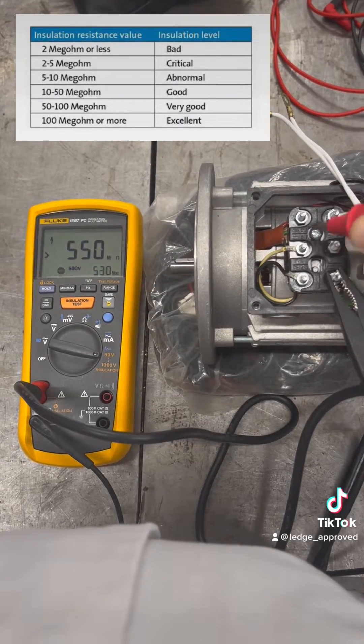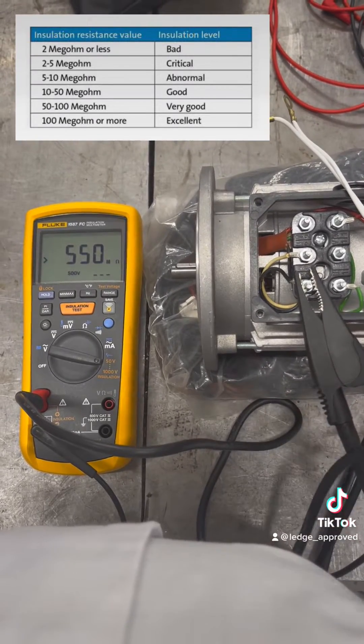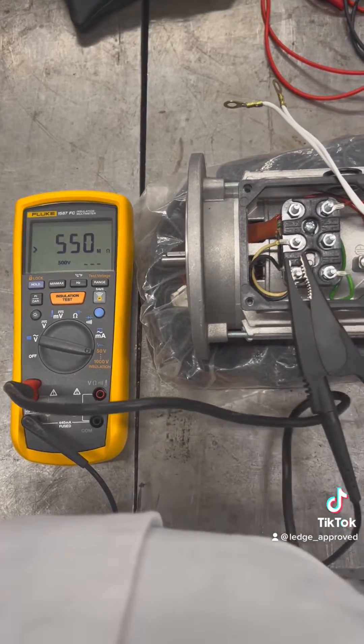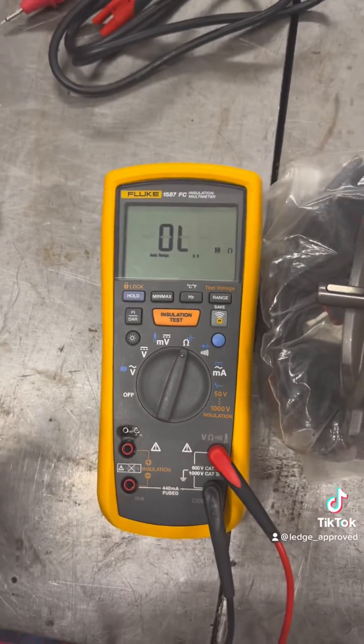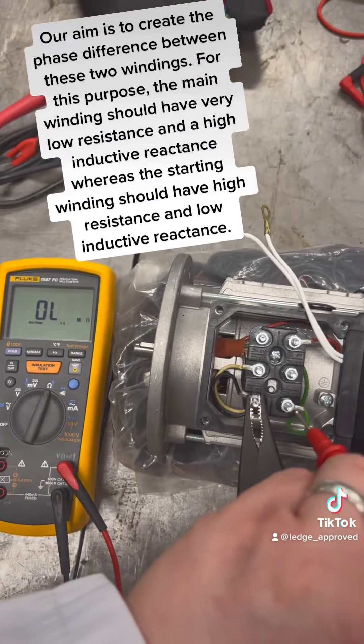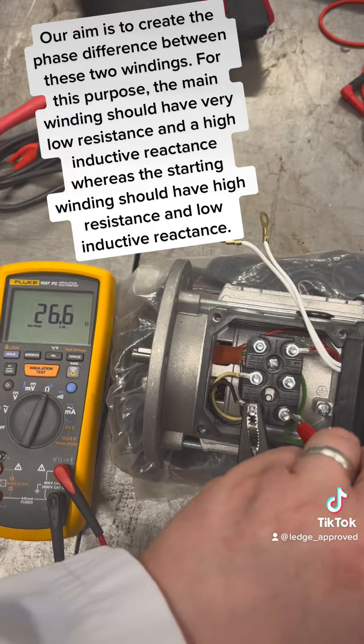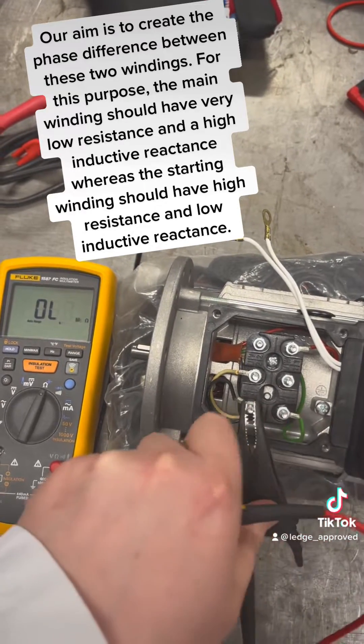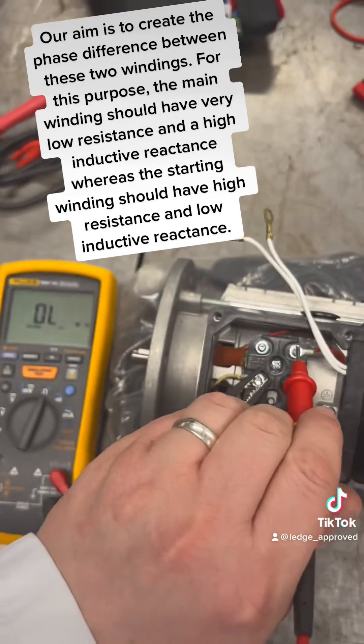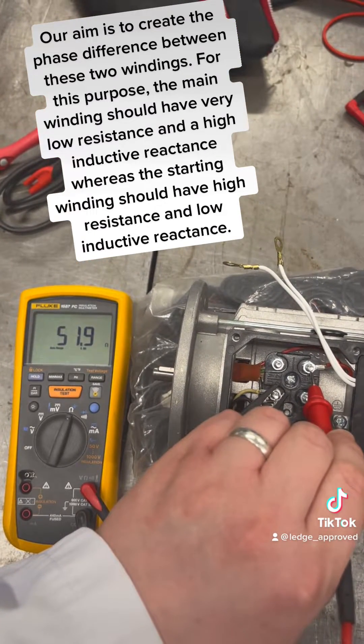On this one it checks out fine. So we're going to check the two phases. On the first one — the main winding — we want low resistance and high inductive reactance. And then on the second one, the starter winding, we should have high resistance and low inductive reactance. And this checks out all right.